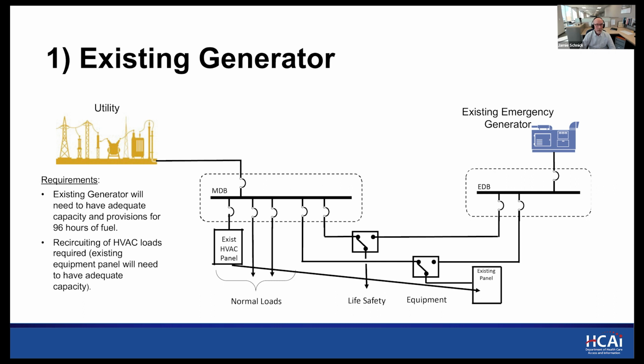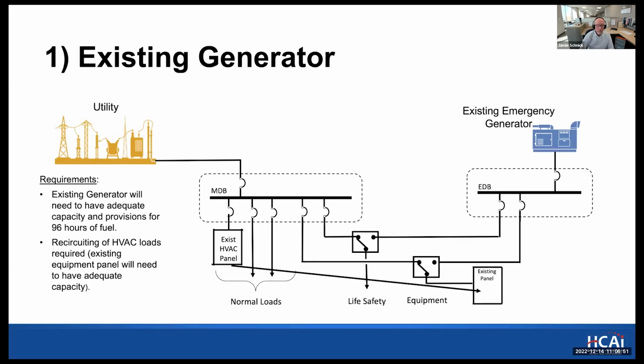This is a quick sketch of the existing generator solution. If the existing generator has adequate capacity, loads could be transferred from the existing normal HVAC panel to the existing emergency panel, in which case all requirements of the new bill would be met, with the exception of the 96 hours. So the facility would have to work on the 96-hour requirement for their existing generator.